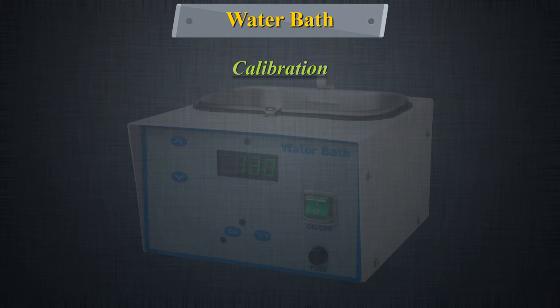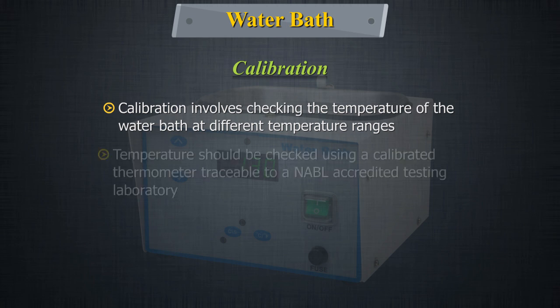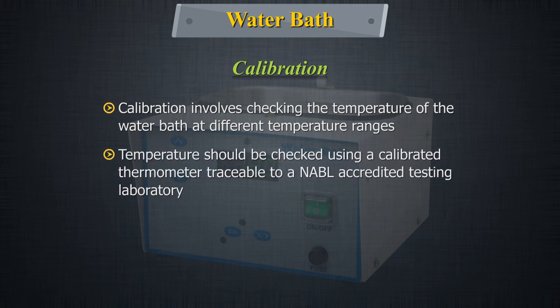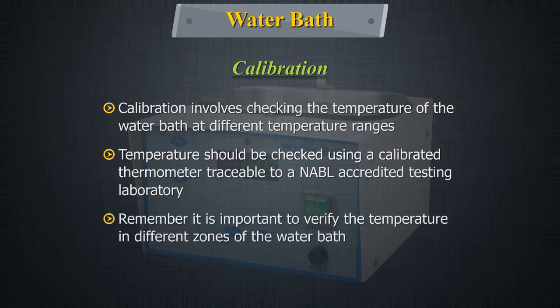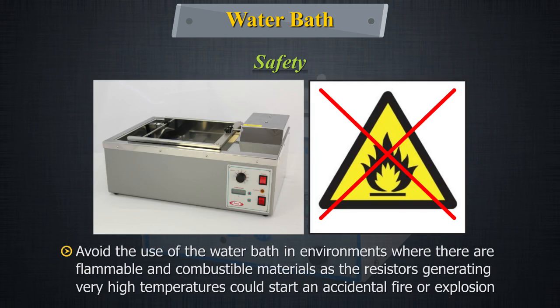Calibration involves checking the temperature of the water bath at different temperature ranges. The temperature should be checked using a calibrated thermometer traceable to an NABL accredited testing laboratory. It is important to verify the temperature in different zones of the water bath.